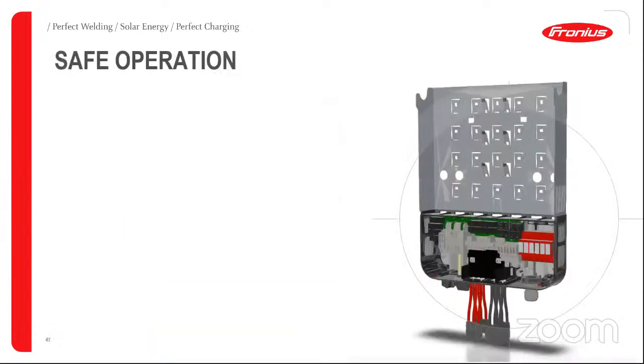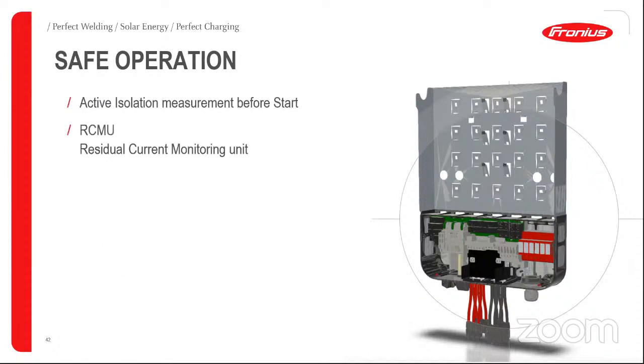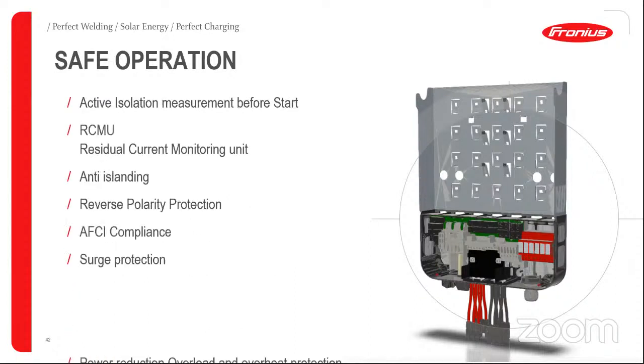Very important also is the safe operation of our devices. All of them, before starting the operation, look for the specific conditions. When everything is okay, they start the operation. We do have these AFCI requirements. This is only needed for the United States market, but we have this for all our inverters because it's an extra safety feature. This feature can detect an arc inside the DC side. So when it happens, the inverter stops the operation and protects the electronics and, of course, protects the whole installation.